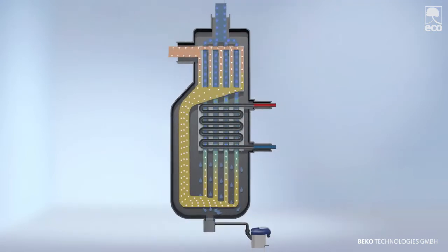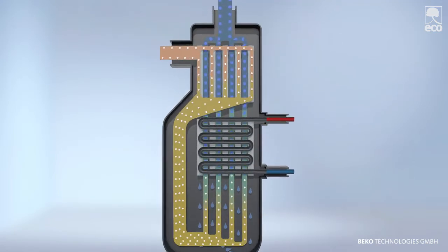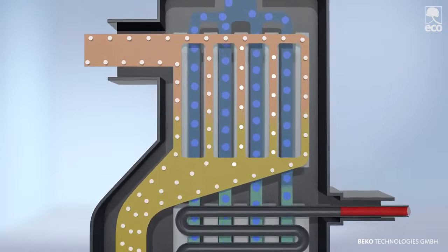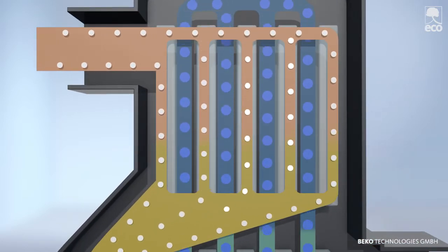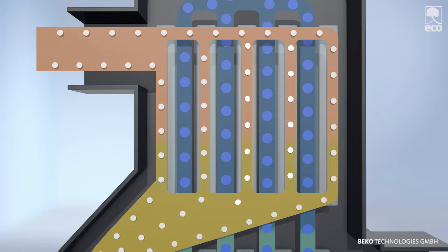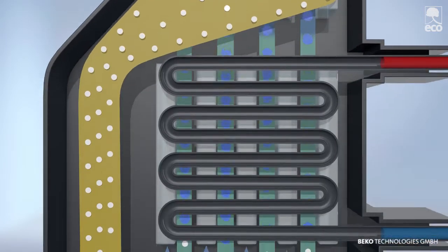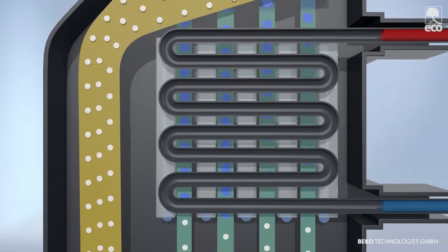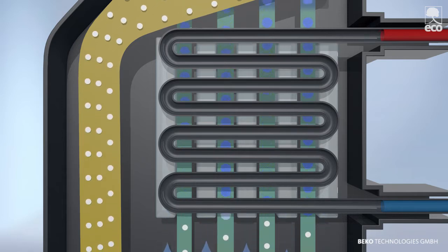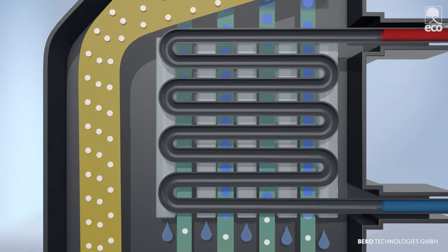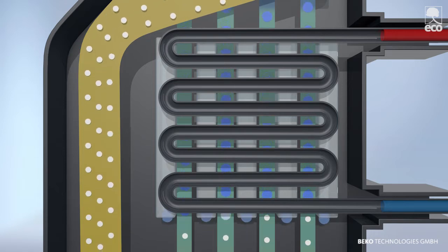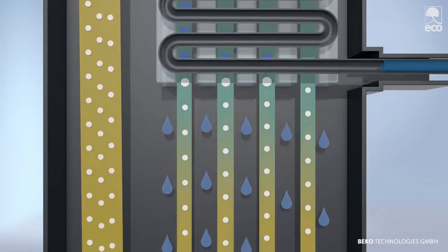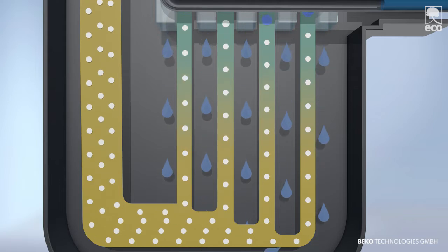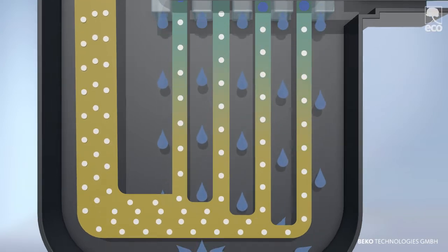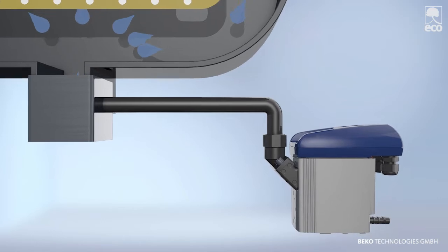Humid compressed air, shown in blue, enters the heat exchanger at the top at about 35 degrees Celsius. There, it is pre-cooled in a countercurrent process by already dry and cooler air. It then flows through the actual cooler, in which it is continuously cooled down to approximately 3 degrees Celsius. The cold temperature reduces the compressed air's ability to absorb water. The ideally dimensioned demister removes 99% of the water droplets. The condensate then simply flows into the integrated Beko condensate drain, and all without the loss of compressed air.